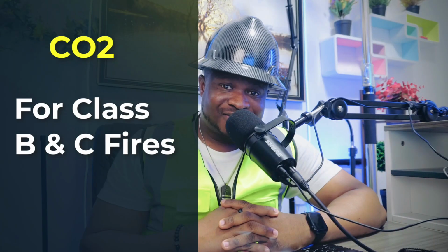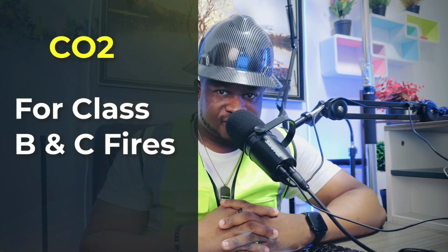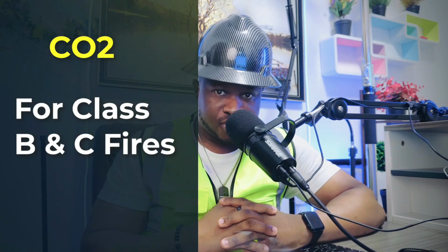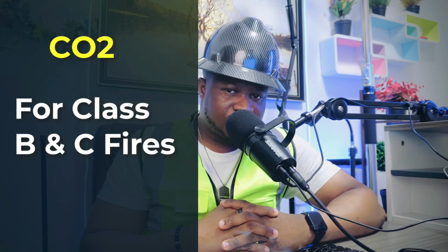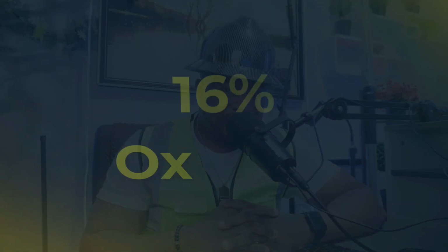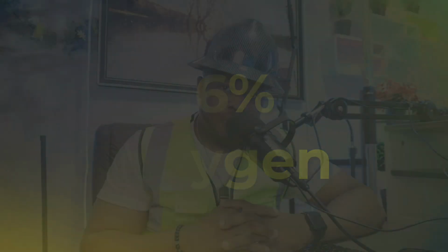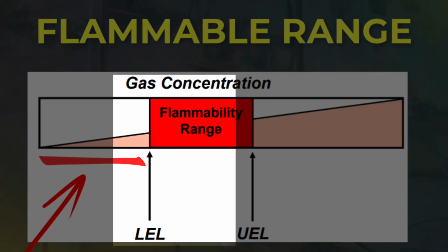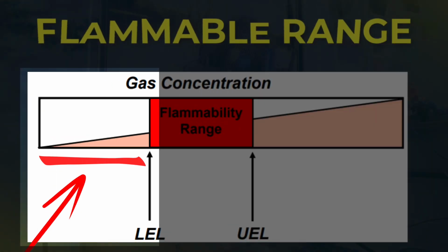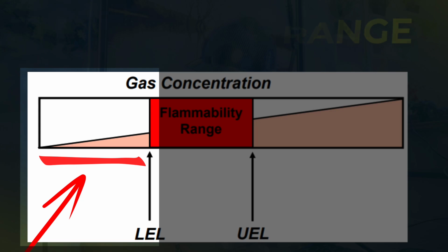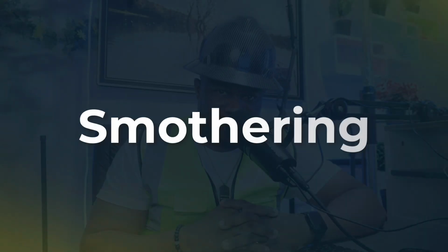CO2 is used for Class B and C fires. These are fires involving flammable liquids and flammable gases. CO2 reduces the oxygen concentration that is ideal for burning. Remember, fire needs at least 16% of oxygen to burn. Once CO2 is introduced, the amount of flammable gas mixed with air is reduced, and that moves the fire out of its flammable range, precisely a level below the lower explosive limit where the fire can no more be ignited. That is smothering also, as we deprive the fire of oxygen.